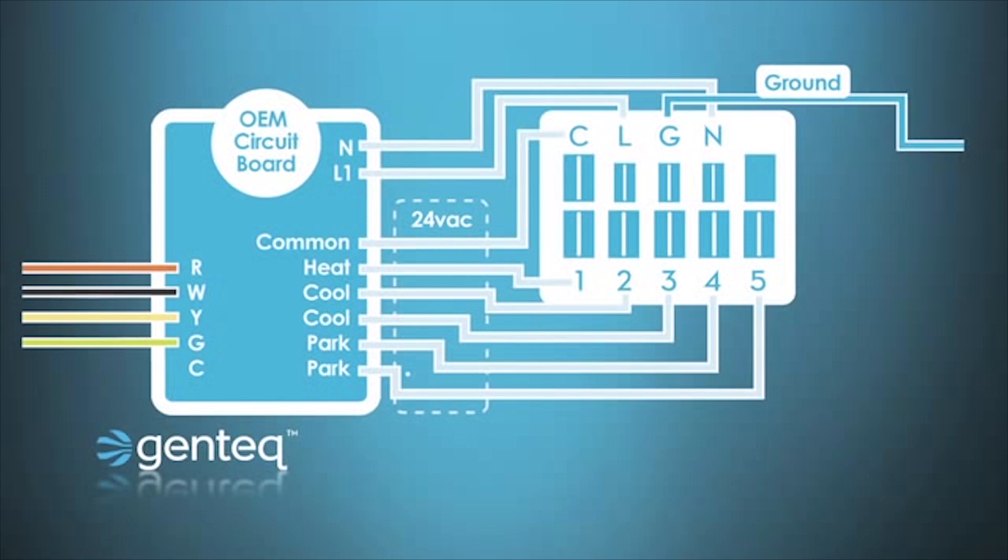If you look at this at a quick glance, you might think well that looks really the same as a PSC motor other than the line, ground, and neutral connections on the motor. But what you'll notice if you look at the schematic for the system or measure voltage is that the voltage going to taps one through four is 24 volts, which is very different than a PSC motor.